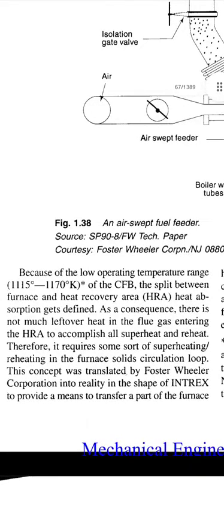As a consequence, there is not much leftover heat in the flue gas entering the HRA to accomplish all superheat and reheat. Therefore, it requires some sort of superheating and reheating in the furnace solid recirculation loop.